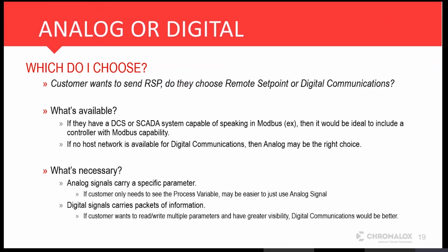Okay, so that's what to look for with digital communication. Now another question I've gotten fairly frequently is, what do I choose? Do I use analog? Do I use digital? What's the right choice for me? And really, it comes down to two questions you can ask. First is obviously what's available. If a customer has a DCS or a SCADA system and they have the capability for, for example, Modbus, then maybe that is the right way to go because they have the functionality there. They're probably using Modbus for other things. Maybe it's just easier for them to integrate that into our controllers.